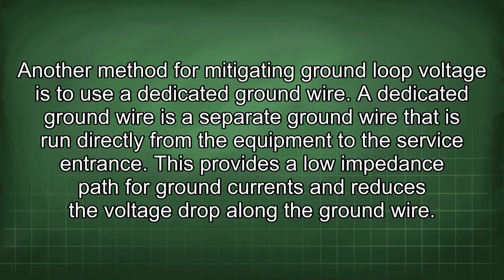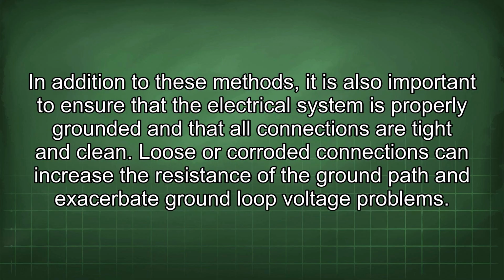Another method for mitigating ground loop voltage is to use a dedicated ground wire. A dedicated ground wire is a separate ground wire that is run directly from the equipment to the service entrance. This provides a low impedance path for ground currents and reduces the voltage drop along the ground wire. In addition to these methods, it is also important to ensure that the electrical system is properly grounded and that all connections are tight and clean.